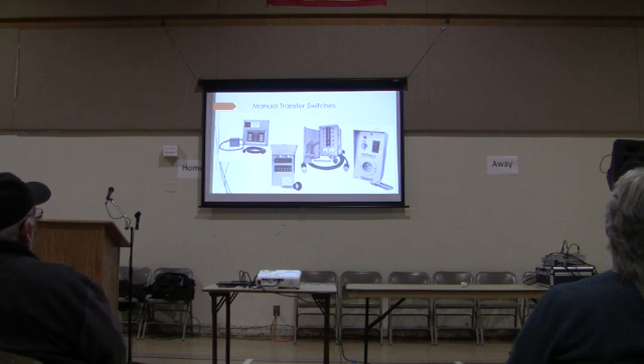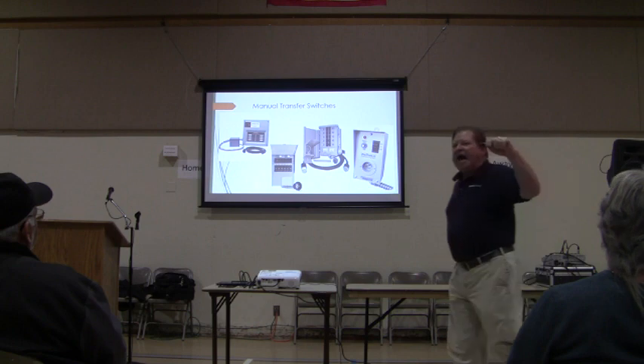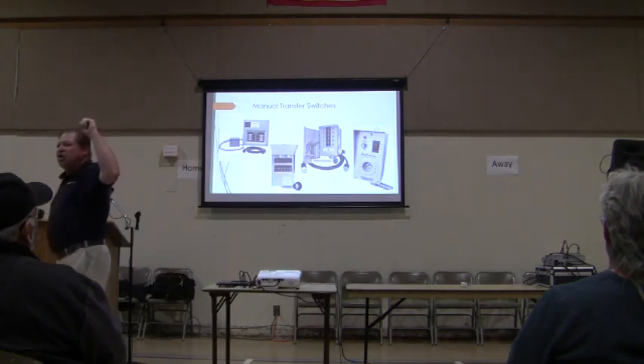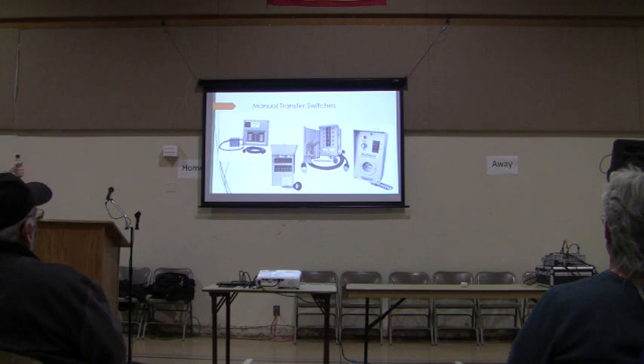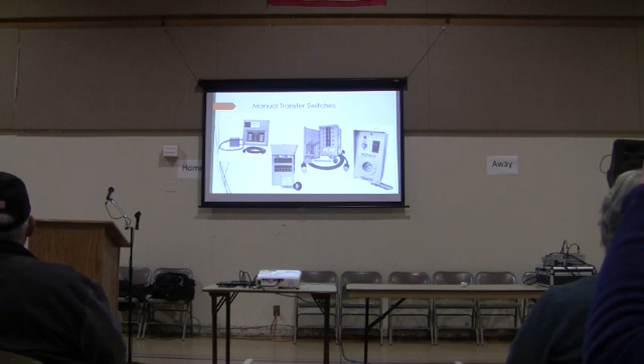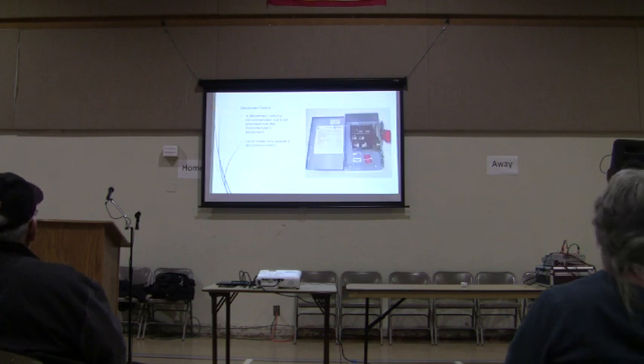Okay, $400. But he's going to pull the permits, and it's permanently wired in, and you've got one place to plug this thing in. That's it. No extension cords to trip on through the house. And then what I would do is turn on one circuit that is not connected to this, that's connected to lights somewhere. And when those lights come on, I know power is back. Because it's a manual switch, it's not going to switch back on its own. I also would recommend a disconnect in the line as well. You don't have to have one necessarily, but I would recommend it.